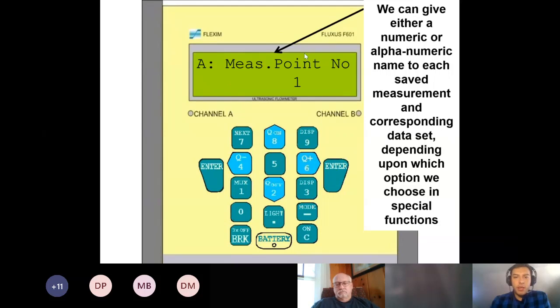This right here is the next screen. It says measure point number. This is a tag, so this doesn't affect the measurement at all. This just tells you that your data logger is on, and it's telling you that when you pull your data, your data for channel A is going to be measuring point 1. You can change this to whatever you'd like. You would hit enter.